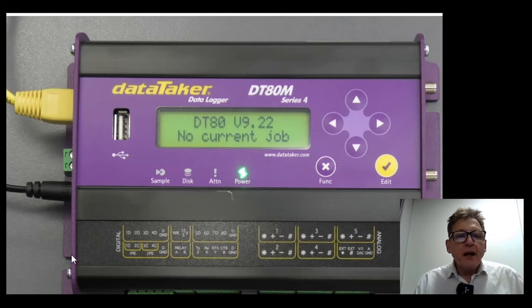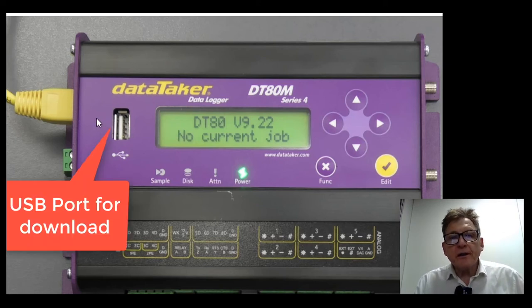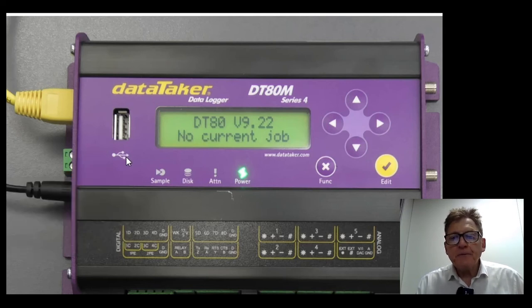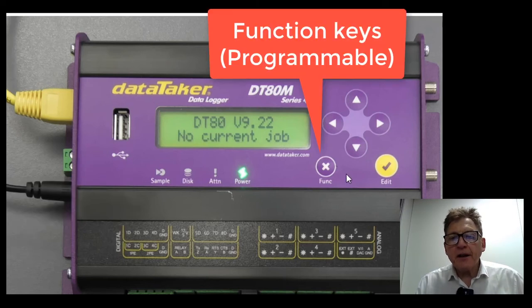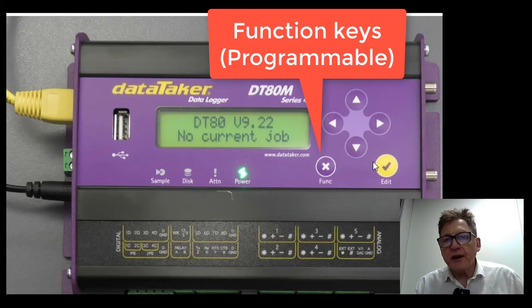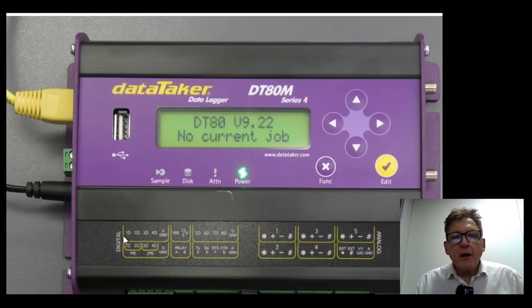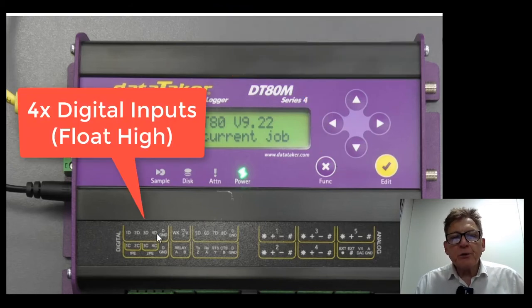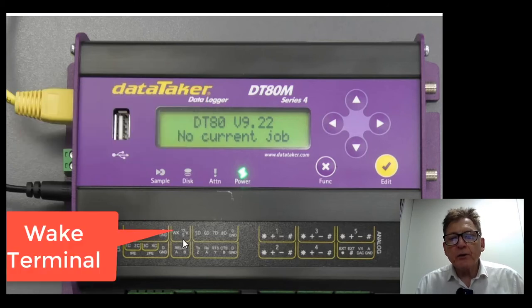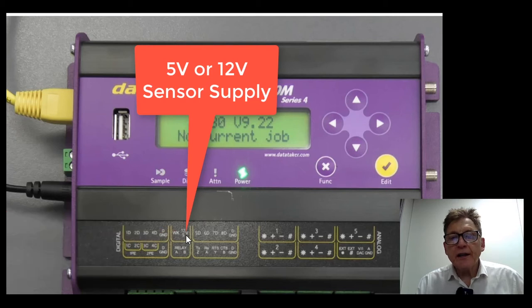Coming across here we've also got a USB port at the top of the unit whereby we can use this for download. A couple of function keys you can program up for various operations on the logger. Four digital inputs here, they float high. This is a wake terminal, this is a power supply, a 12 volt or 5 volt power supply for external sensors.